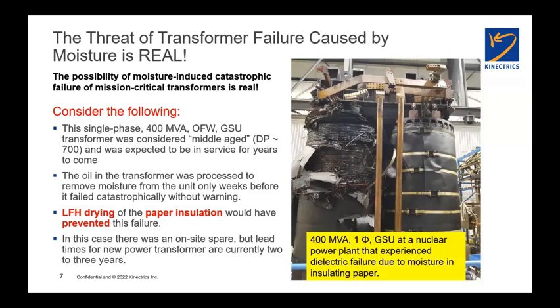The transformer itself was quote unquote middle aged. We can do a furanic compound assay on the oil. It's one of the tests you can do on oil. And from that, we can infer the degree of polymerization of the paper. I'll talk more about that in a couple of slides. But the DP in this case was 700, which is about middle of the road and indicative of, again, what we would consider to be a middle-aged transformer. So it had lots of lifespan remaining and no reason for it to fail prematurely.